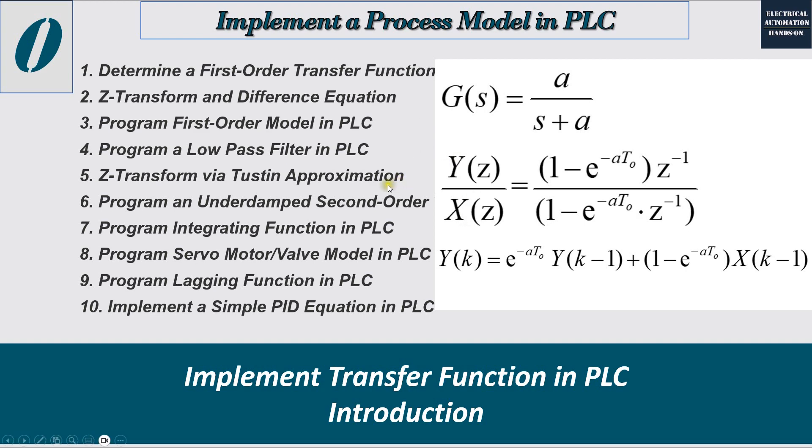Other than the first order and second order system, I will also introduce the commonly used methods. How can we program a low-pass filter for PLC? For example, if you are using PLC to receive the analog signal for temperature or pressure, and if the analog signal has high noise, how can we implement a very simple equation to filter the noise? And I will also introduce how we can implement the integrating function. For example, for the servo motor positioning feedback, they definitely need to use the integral function. So how can we program the integration into the PLC? Then we can implement the function for the servo motor or servo valve model into the PLC.